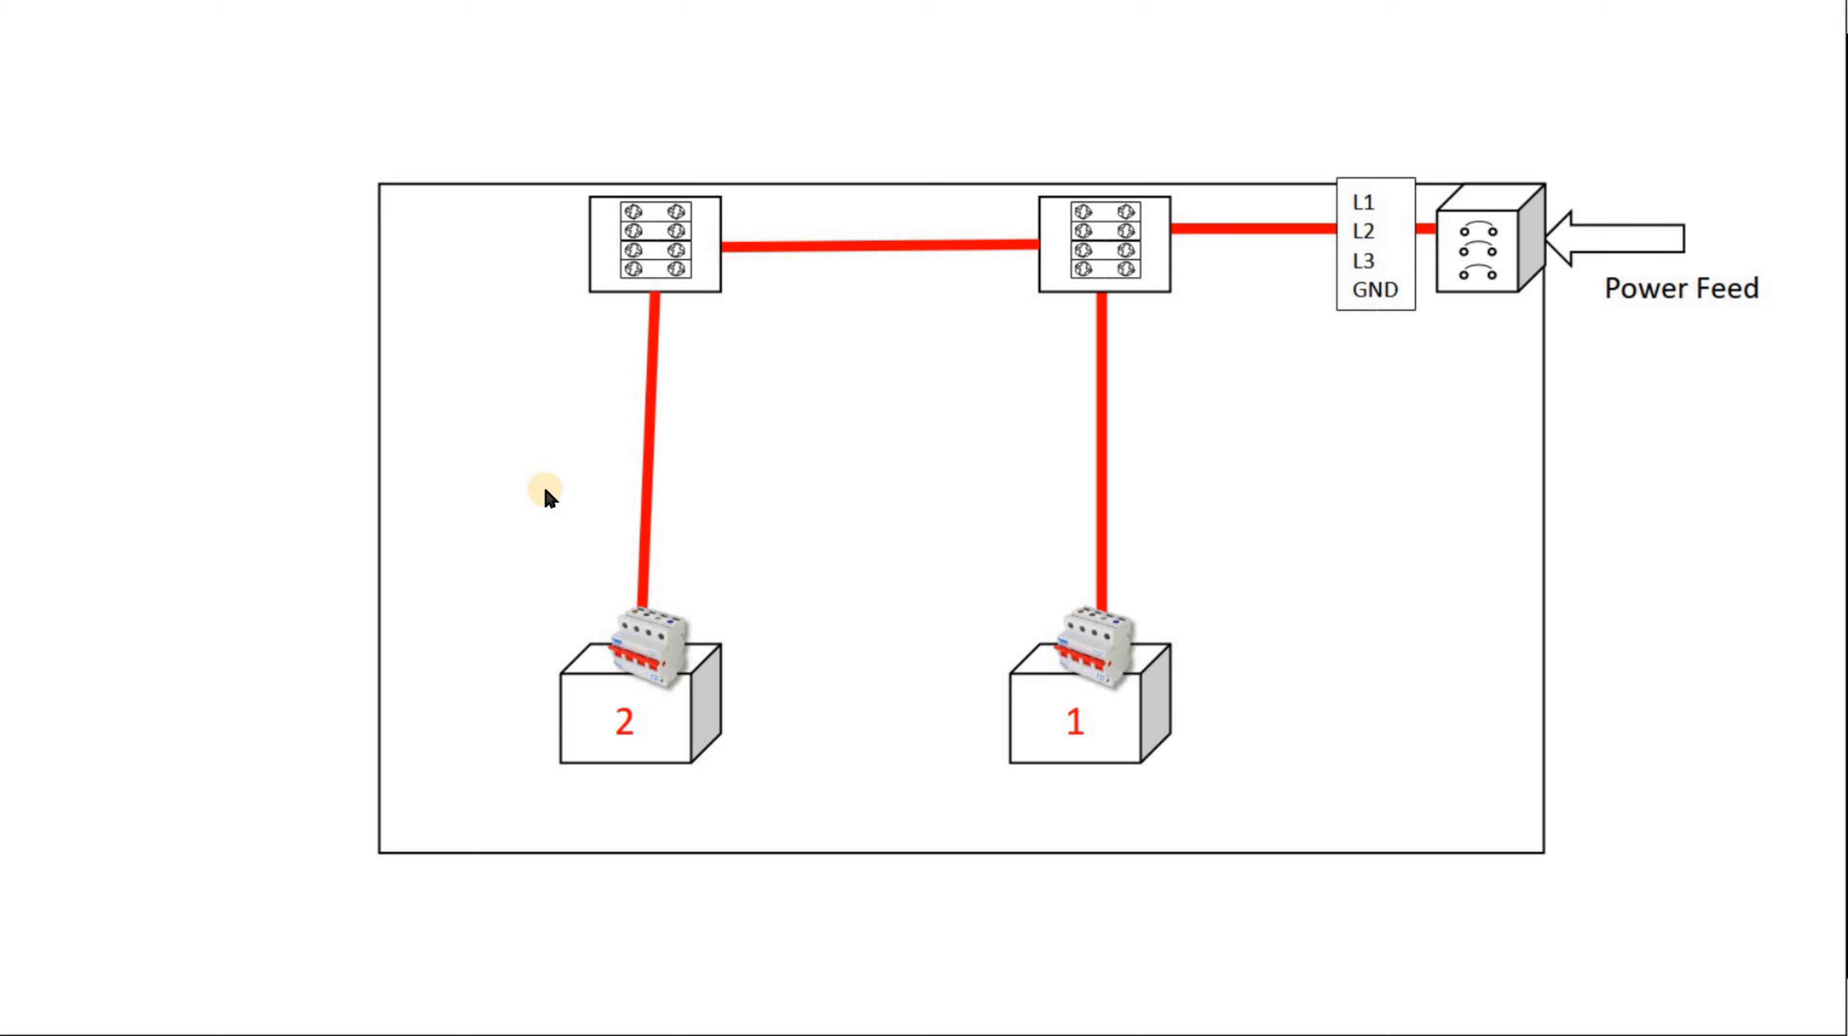What happened in this small manufacturing facility is they have one cable going from the main feed to a junction box, and then from the junction box you have feed to each machine. So you have one switch in each machine and main circuit breaker.